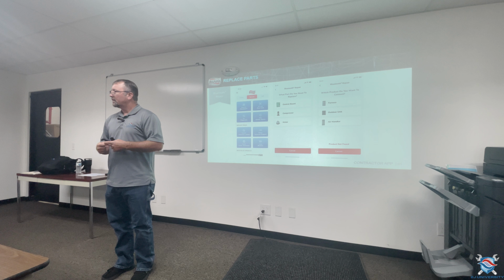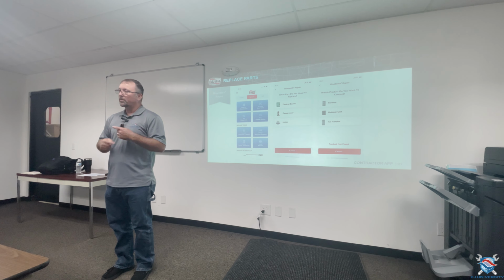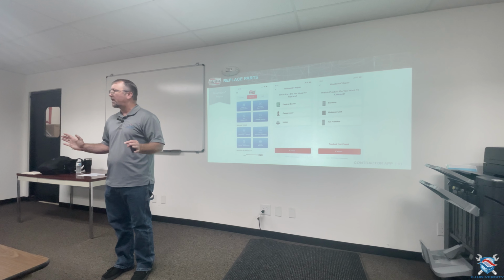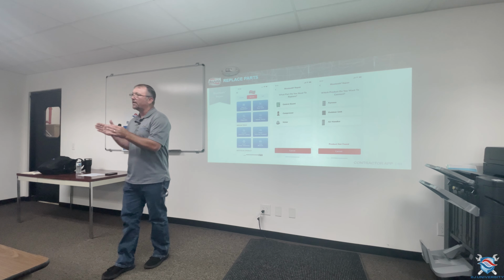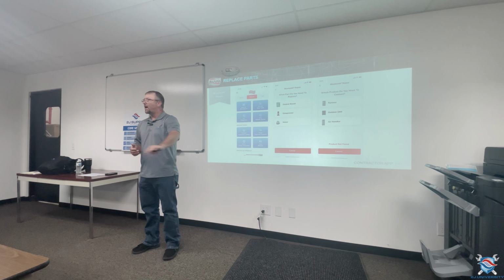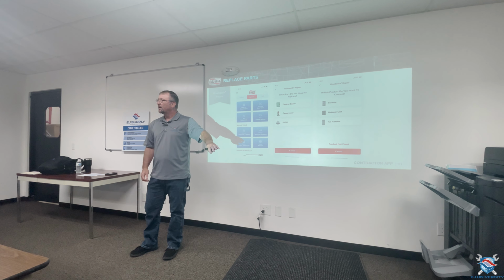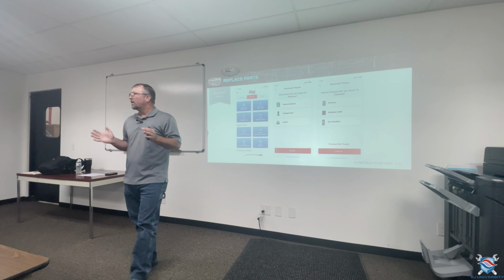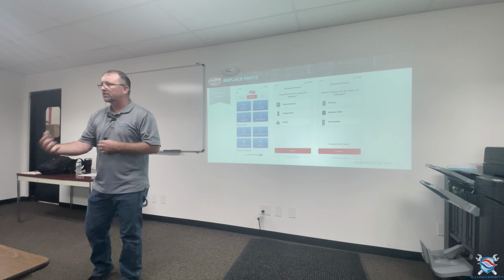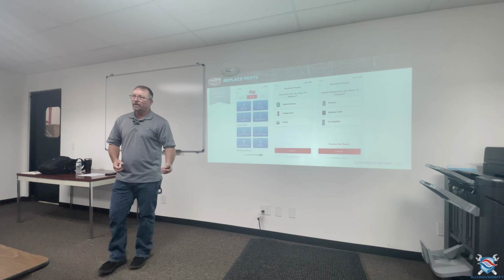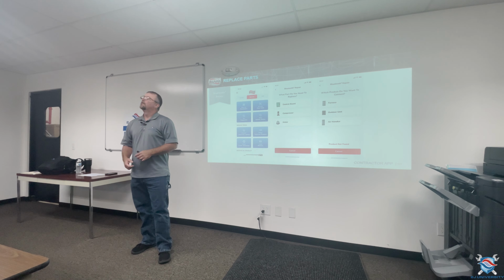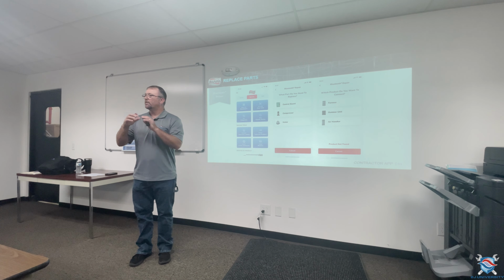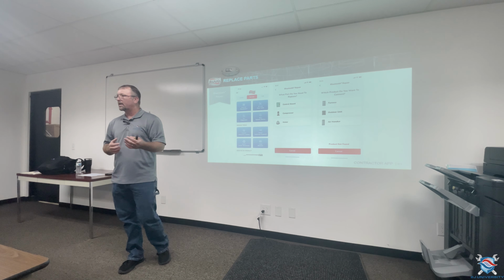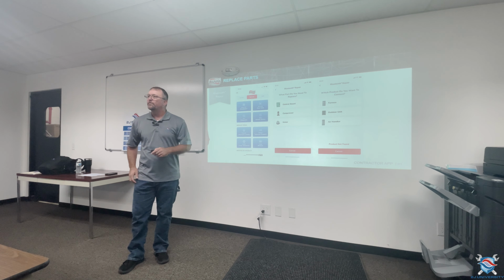Once you've done that, it'll set the RPM range for it and everything will run fine and it'll stay. I don't know if it's because when they flash them at the factory and then they're powered down for a period of time that it's losing the memory. I don't know, but I've had this call numerous times, and I'm just trying to let you guys know, if you get out there and you get a condenser fan motor fault, uninstall it, reinstall it through the app, and then it'll flash it to the control board on the outdoor unit, and everything's going to run fine for you.